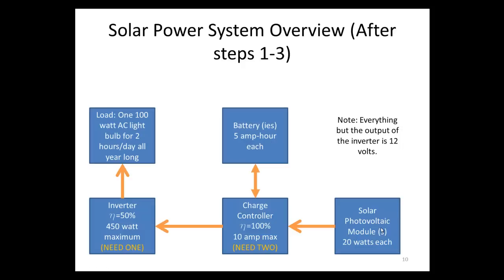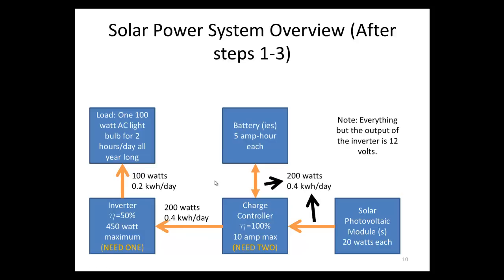To review what we've done so far: we found that we need one inverter and two charge controllers. Going to the load is 100 watts when it's on, and the energy needed is 0.2 kilowatt hours per day. When the light bulb is on, the inverter draws 200 watts from the charge controller, and the energy coming from the charge controller is 0.4 kilowatt hours per day. That means we need to supply 0.4 kilowatt hours per day — either from the battery or from the solar modules.